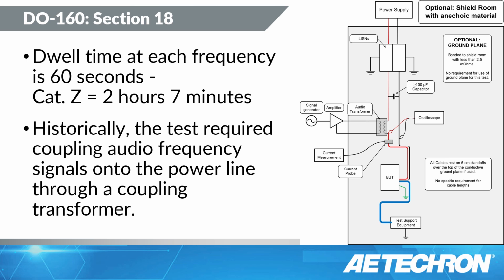Now we want you to dwell at each one of those frequencies for 60 seconds because we're looking for filter harmonics or filter resonances that can cause heating. And if your filter goes into a resonance and we dwell at that for a period of time, it can create a situation or an issue with your input filter. And that's what we're looking for. We want to make sure that that's not going to be the case.